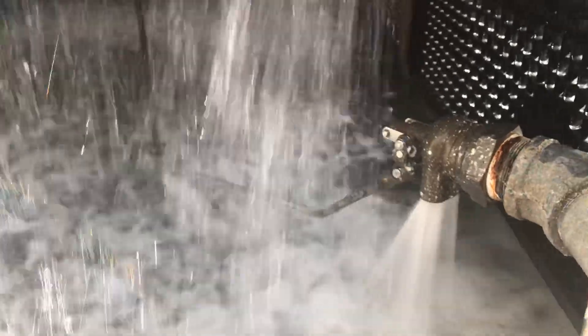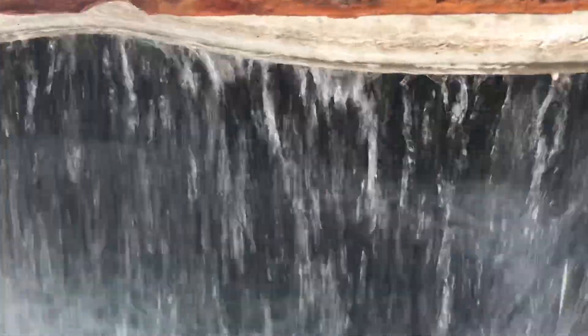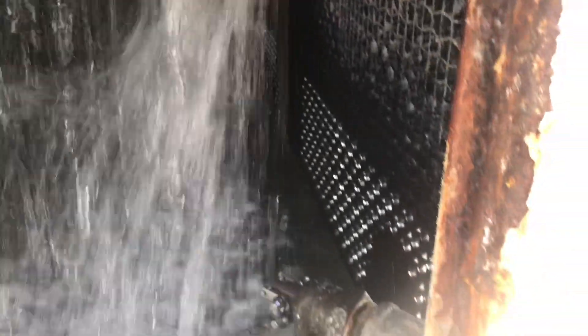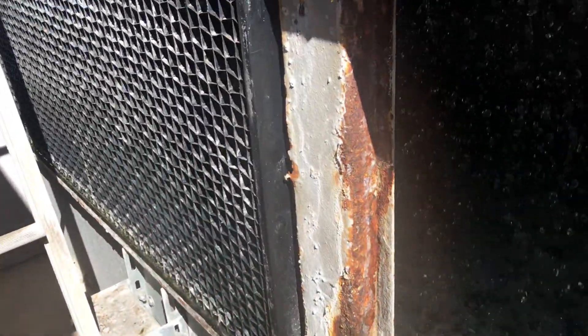So that's a concern. I may give him a quote to replace it. This fluid cooler's got some heavy rust — you can see the rust right there. It's definitely got some stuff going on, some heavy rust.